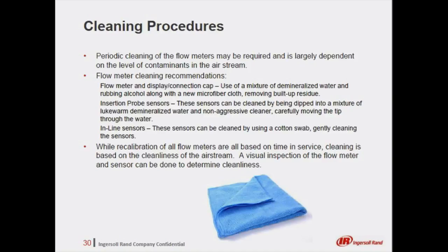While recalibration of the flow meters is based on time in service, cleaning is based on the cleanliness of the airstream. A visual inspection of the flow meter and sensor can be done to determine cleanliness.